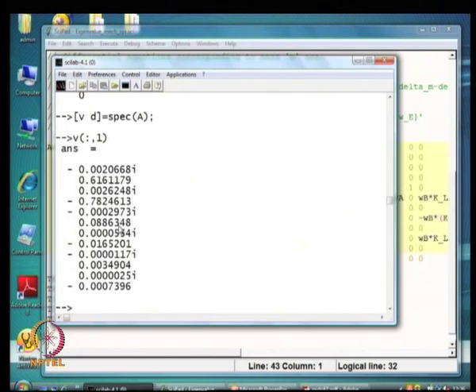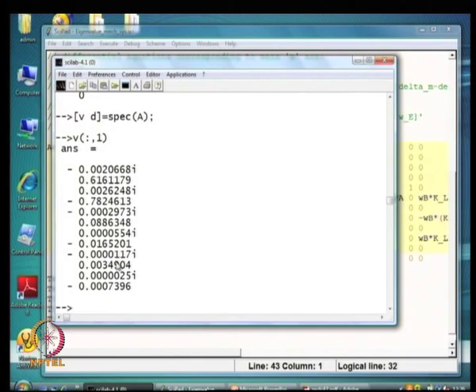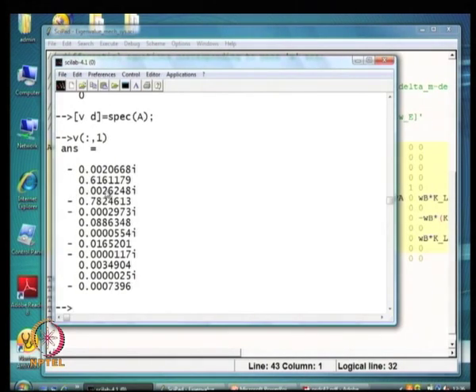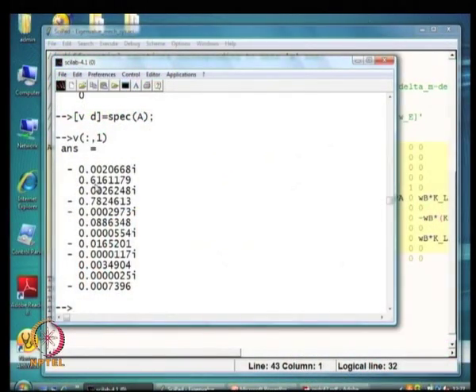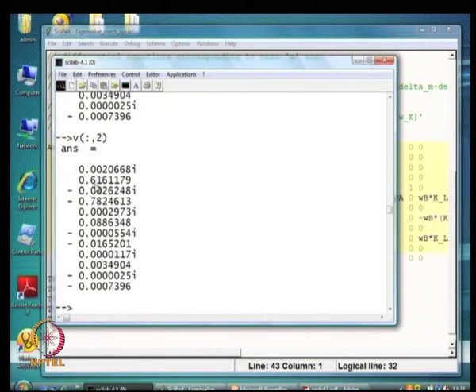You notice that different masses have different observability in this mode. For example, this mode is not very well visible in the last four states — delta_generator, omega_generator, delta_exciter, and omega_exciter. Also you notice the delta component for HP is negative while for IP it is positive, meaning when one mass goes ahead, the other goes behind. If you look at the second mode, it will have some other property, and so on.